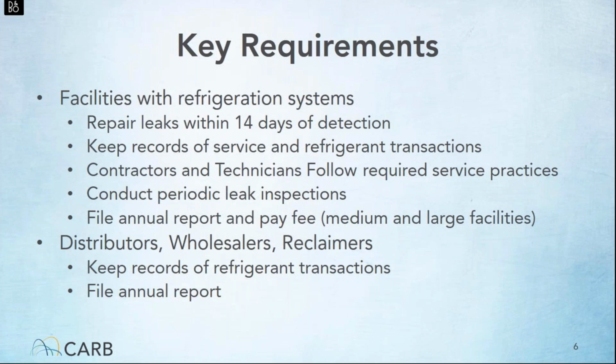This includes prompt leak repairs, which need to occur within 14 days of the initial detection of the leak. Records also need to be retained on site, and required service practices are also in effect. Leak inspections are required, but the frequency depends on the size of the system. Small systems must have an annual leak inspection, which should occur around the same time every year.